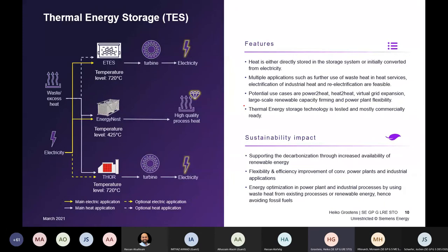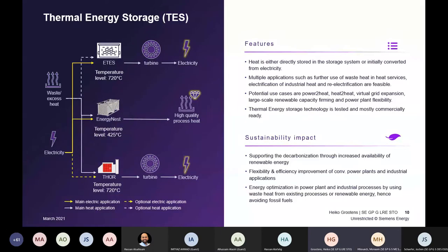Turning to thermal energy storage: the product portfolio includes ETES from Siemens Gamesa, the EnergyNest thermal battery, and THOR — an in-house development especially for integration with combined cycle power plants. The key differences are temperature levels and loading modes: ETES and THOR can store energy at up to 720 degrees Celsius, while EnergyNest is currently limited to 380 degrees. ETES is primarily charged via surplus renewable electricity, while EnergyNest is charged directly with thermal energy, and THOR is particularly suited to be loaded with exhaust gas.